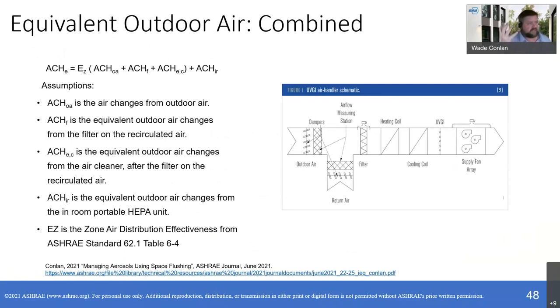Well, they get the outdoor air piece, but what we're trying to say is if we have other items that we can use to create equivalent outdoor air, the ACHE, right? Everyone uses acronyms slightly different. And so you can see that formula on the top, right? It's taking the air changes of OA, it's taking the air changes of the F, which is the filter, and it's taking the air changes of the EC, which is the air cleaner.